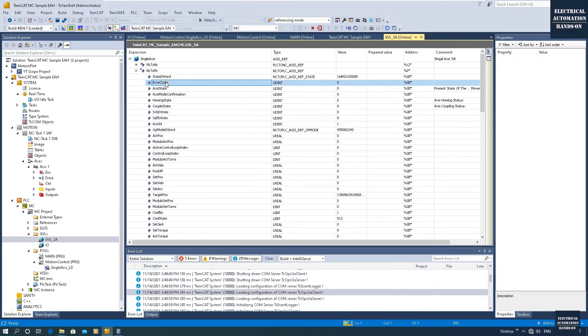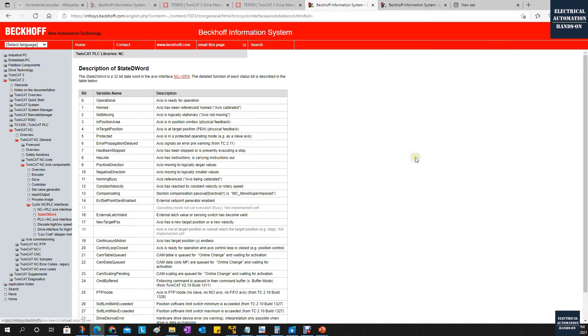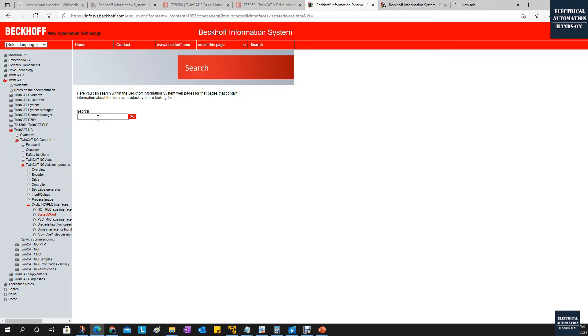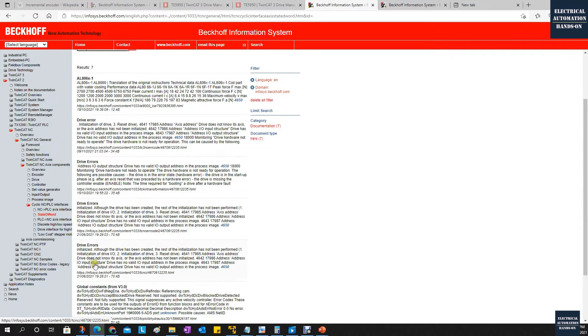Other than the StateDWORD, the error code is also an important status. The error code showing here is an integer. Going online, the error code shows in hex, and below it shows the decimal value. We can use the error code to diagnose what's going on with the axis. For example, going back to the Beckhoff Information System and searching here — we can type in 4650 and search to find what this error code means.